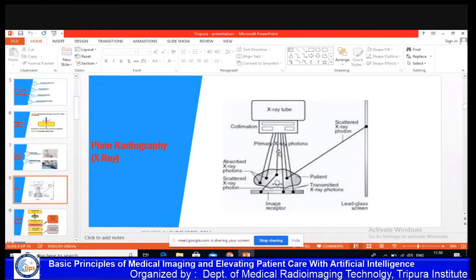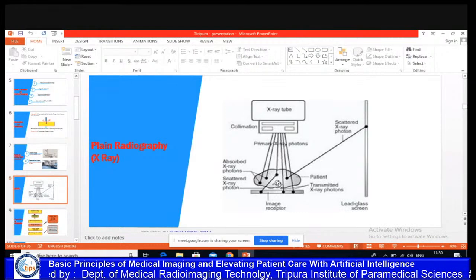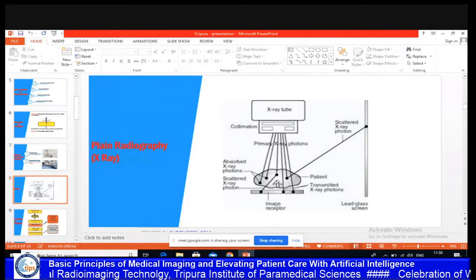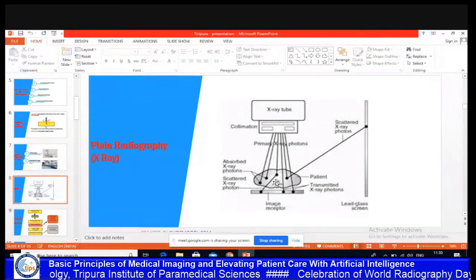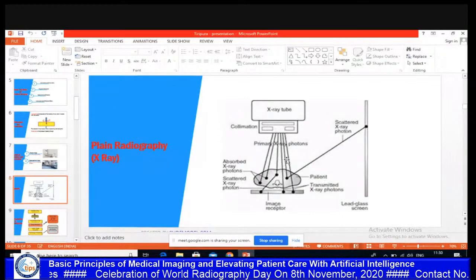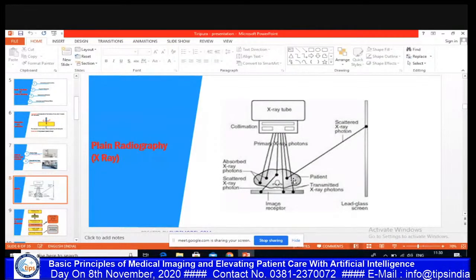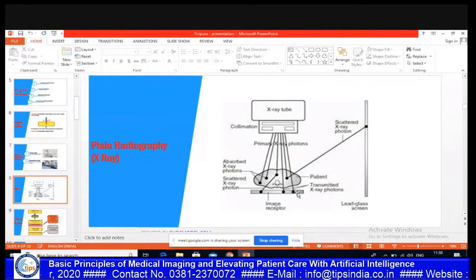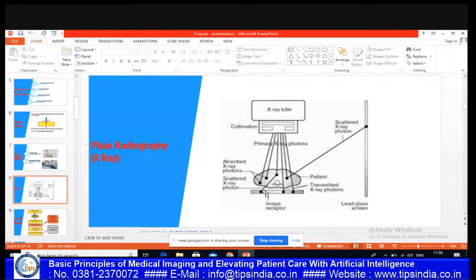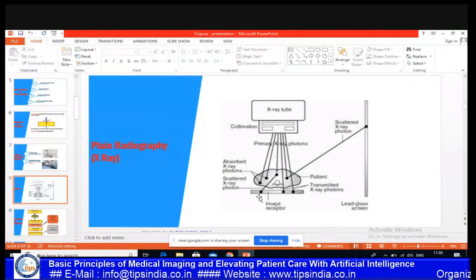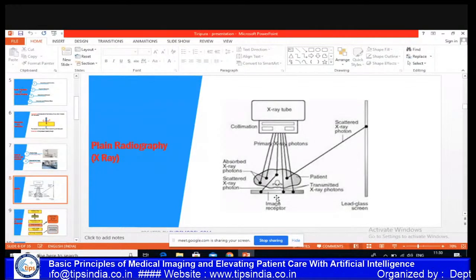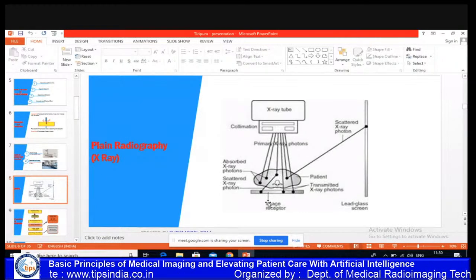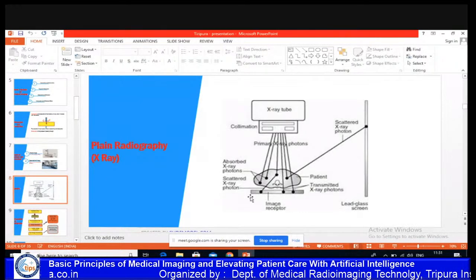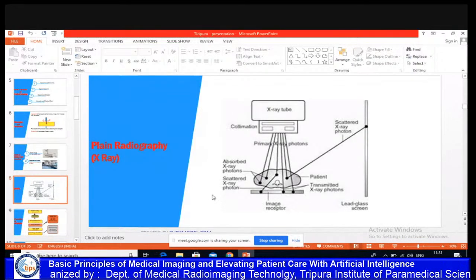When the X-ray passes through the bone, the density of the bone is more, the atomic number is more, so it absorbs more energy, and the penetrated ray will have only less intensity. When it is passing through the soft tissue, it is reverse. That is, it absorbs very less energy, and the penetrated beam will have comparatively more energy. This difference in the intensity of the X-ray makes an image on the image receptor, which is then converted into a readable image. The image formed in the image receptor is in the latent form.